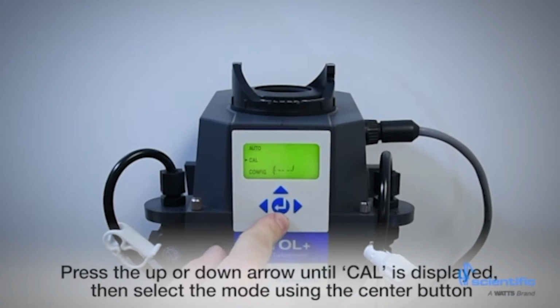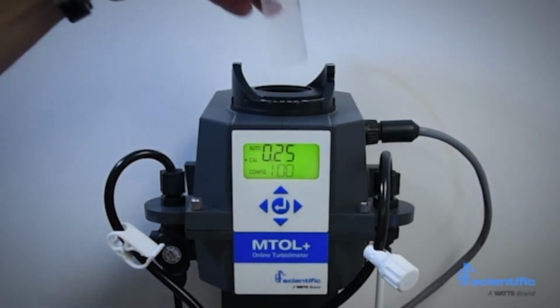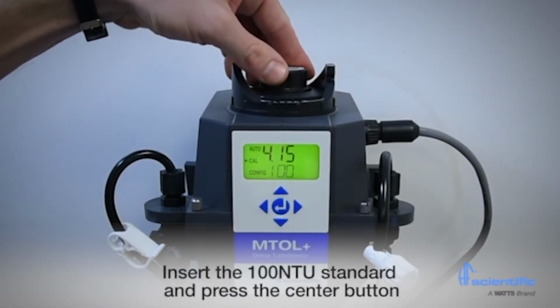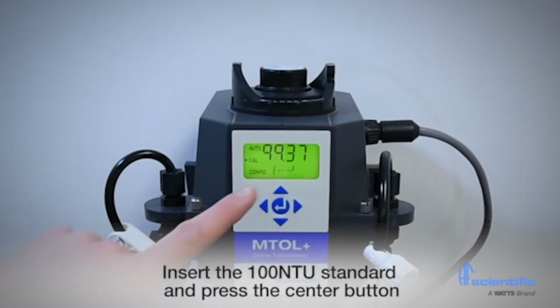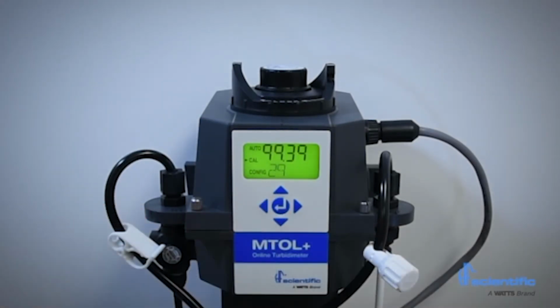To start, press the up or down arrow until Cal is displayed, then select Mode using the center button. The instrument will display 100. Insert the 100 NTU standard and press the center button. The instrument will count down 30 seconds and then will display 100.